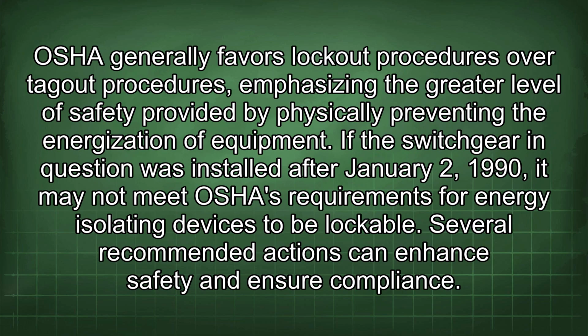OSHA generally favors lockout procedures over tagout procedures, emphasizing the greater level of safety provided by physically preventing the energization of equipment. If the switchgear in question was installed after January 2, 1990, it may not meet OSHA's requirements for energy isolating devices to be lockable.